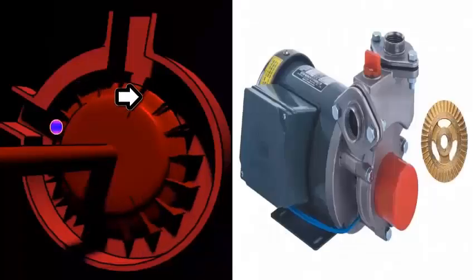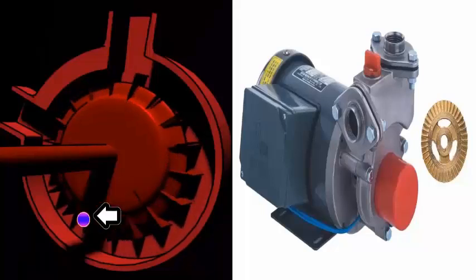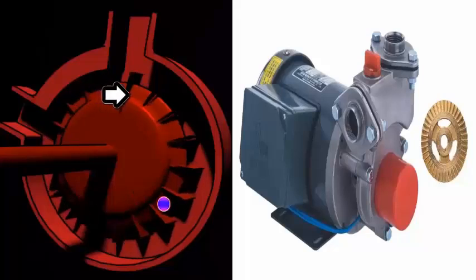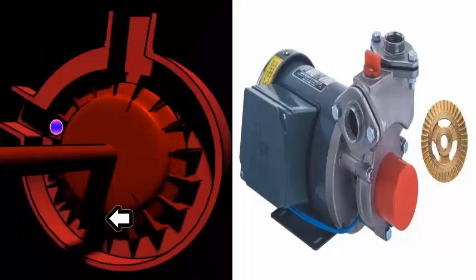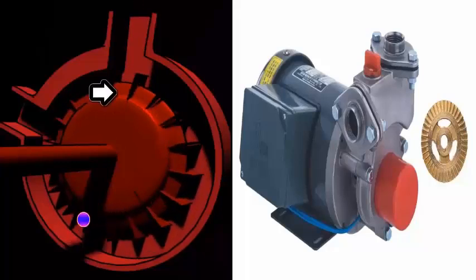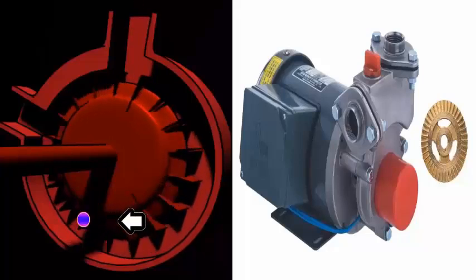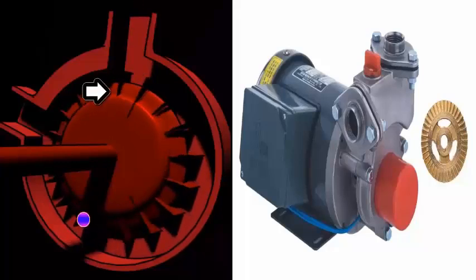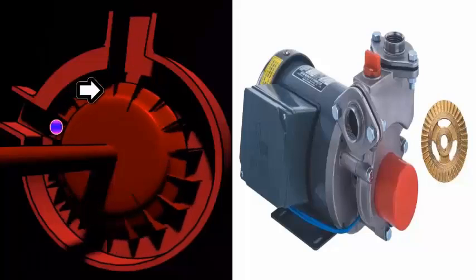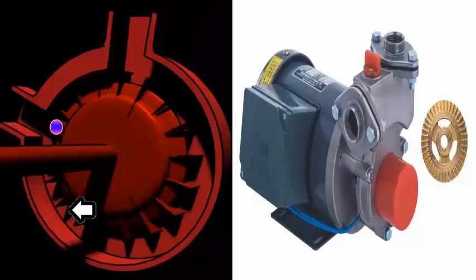Its impeller has small blades that work alongside a narrow channel in the casing. This design forces the fluid to circulate repeatedly inside the pump before exiting. In simple terms, a drop of water can make several loops within the impeller of a peripheral pump, gaining more energy and pressure.